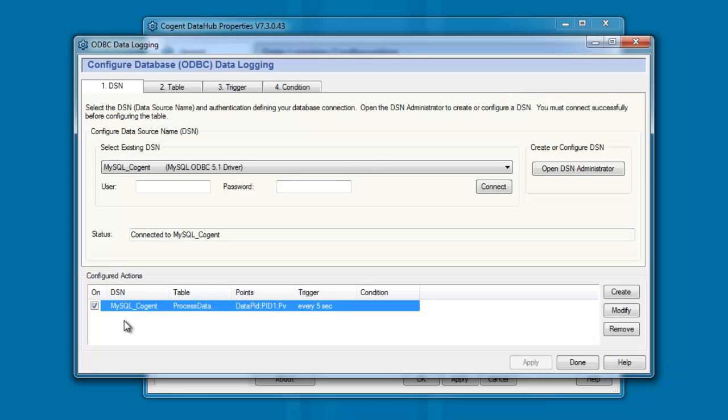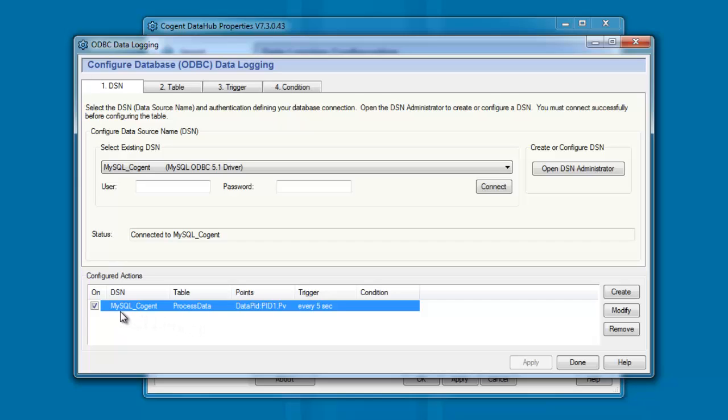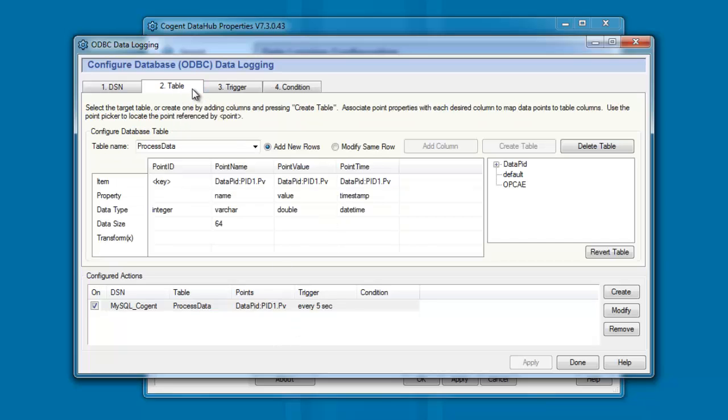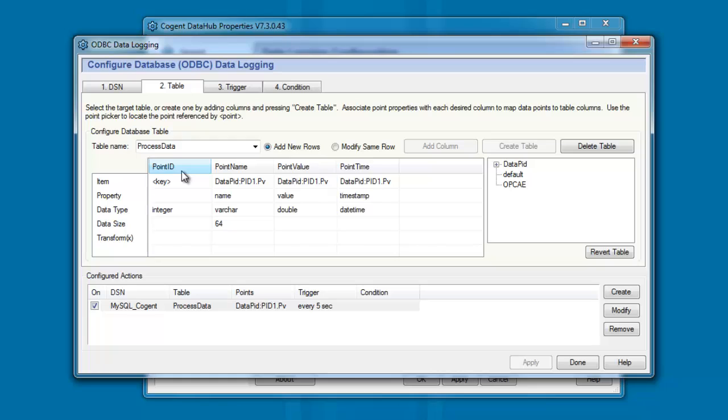This configured action is firing every five seconds, and it's writing the value of DataPID, PID1.pv, into the process data table of the MySQL underscore Cogent database. If we take a closer look at the settings, you can see that when this configured action triggers, we are adding a new row.